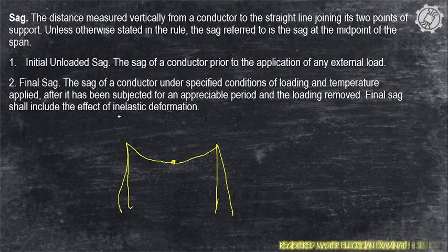So, final sag shall include the effect of inelastic deformation. Kasi kapag palaging may loading, either intentional or unintentional, nagkakaroon ng deformation. Nagiging elongated yung ating wires, at maaaring maputol yung ating wires in the long run.